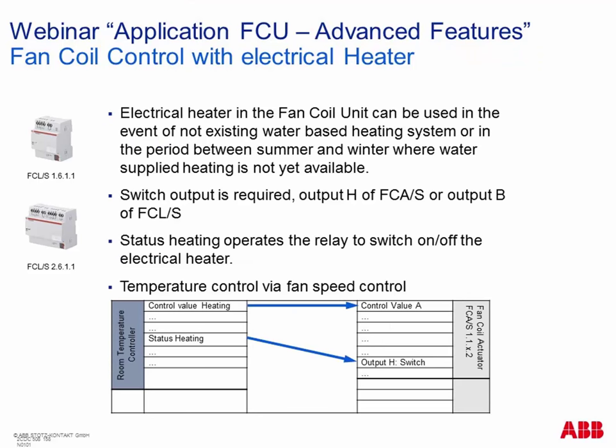Another option is to run an electrical heater with our fancoil actuators. In some cases — for example where cooling is mainly needed and heating only a few times per year — it makes no sense to have a water-based heating system. You take only an electrical heater in your fancoil unit, switch it on and off electrically, and the fan heats the room together with this electrical heater. You can use the output H in our fancoil actuators FCAS, which is a relay output only. You connect the electrical heater here, and via status heating as a group object, you activate this channel, switch on the electrical heater, and control temperature via fan speed. Output H is specifically made for this purpose.